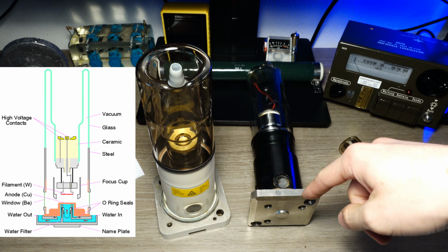But anyway, all of these energies are really low, and they would be completely filtered off if you used a glass enclosure like in this tube. For that reason, all of these diffraction tubes have beryllium windows. As you can see, they have 4 beryllium windows, all at 90 degrees from each other.